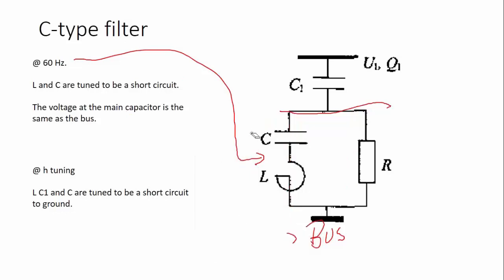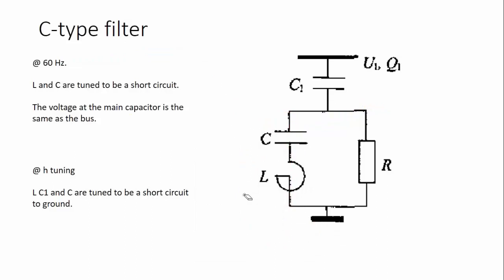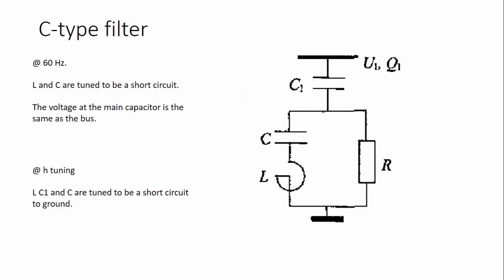And when you analyze that filter from the tuned frequency, which is the frequency that you want to filter out from the system, the whole filter, which means L, C, and C1, the whole thing is tuned to be a short circuit, which is pretty much what a notch filter does to filter out that harmonic, to provide a path of minimum impedance from the bus to the common point for that particular harmonic. So these are the conditions that should be met.